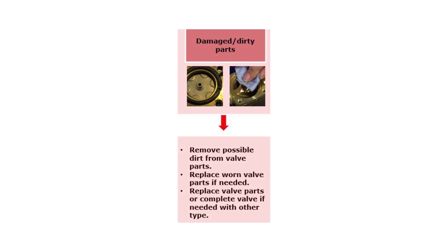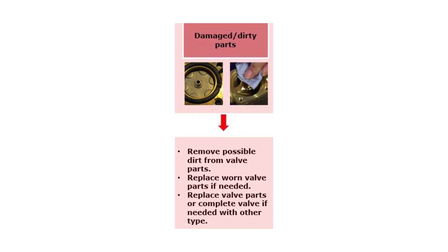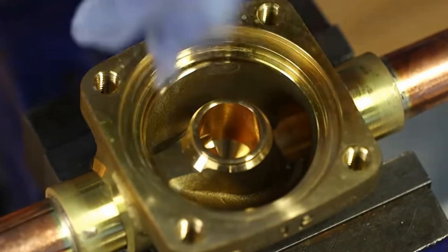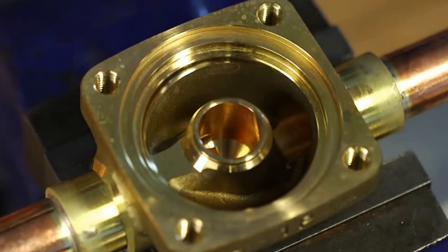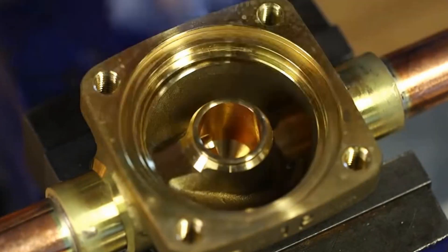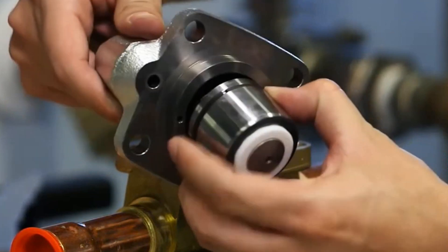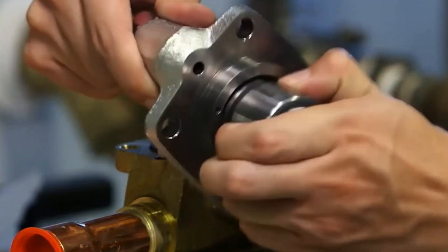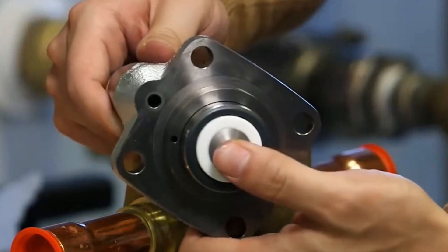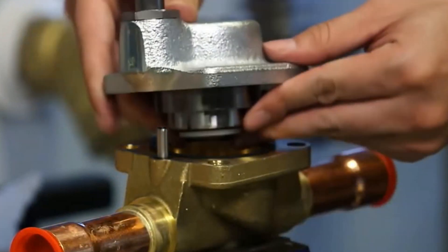Now if there seems to be damaged or dirty parts causing valve external leakage, then as a first step, take the valve apart, if it is serviceable, and clean the internal valve area and parts, as seen shortly here. If needed, replace worn parts using suitable service kits, and check out other Danfoss online videos about solenoid valve service.